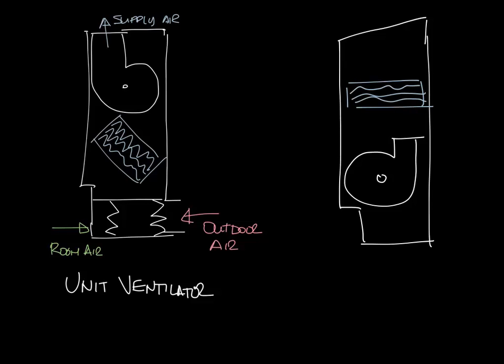So now the room air comes into the front of the fan coil, goes through the blower, through the coil, and then the supply air comes out the top. But you can see there's no outside air inlet on the fan coil.